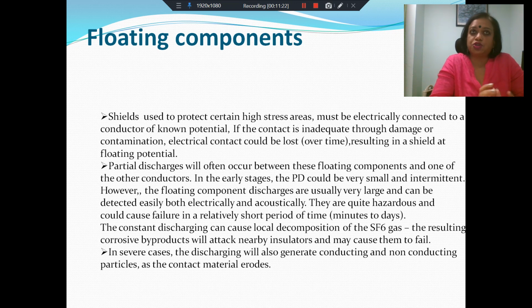And in order to prevent that, we might provide some kind of shields so that the electric stress can be controlled. Now, when you have shields, these are metallic components. These shields do equalize the stress, but the shields have to be electrically connected to a conductor of known potential. As long as that happens, there is no problem. So you are kind of inside the insulator, forcing the potential to a certain level along the insulator. As a result, the stress becomes better graded, and you don't have high field gradients.